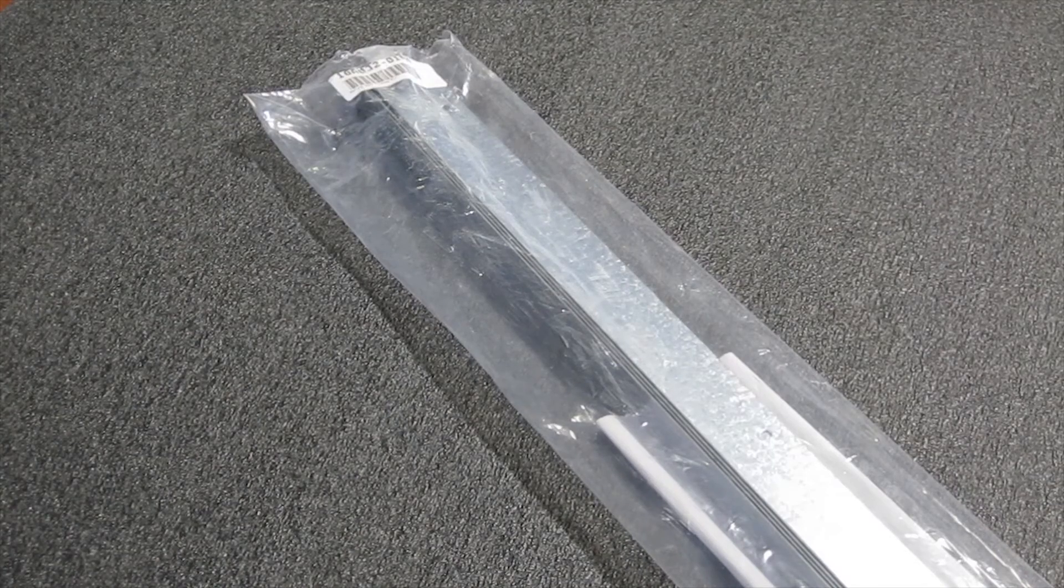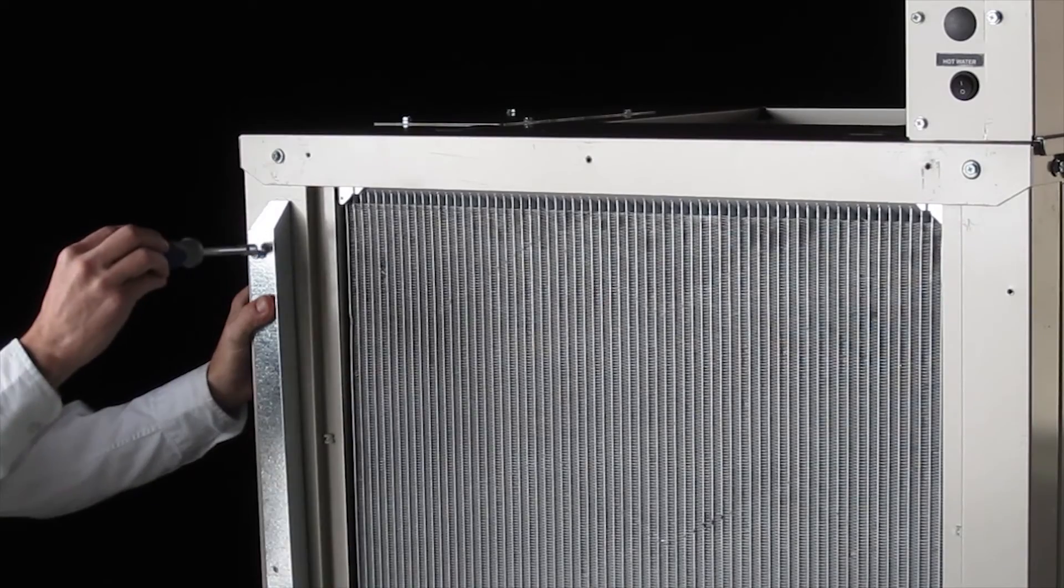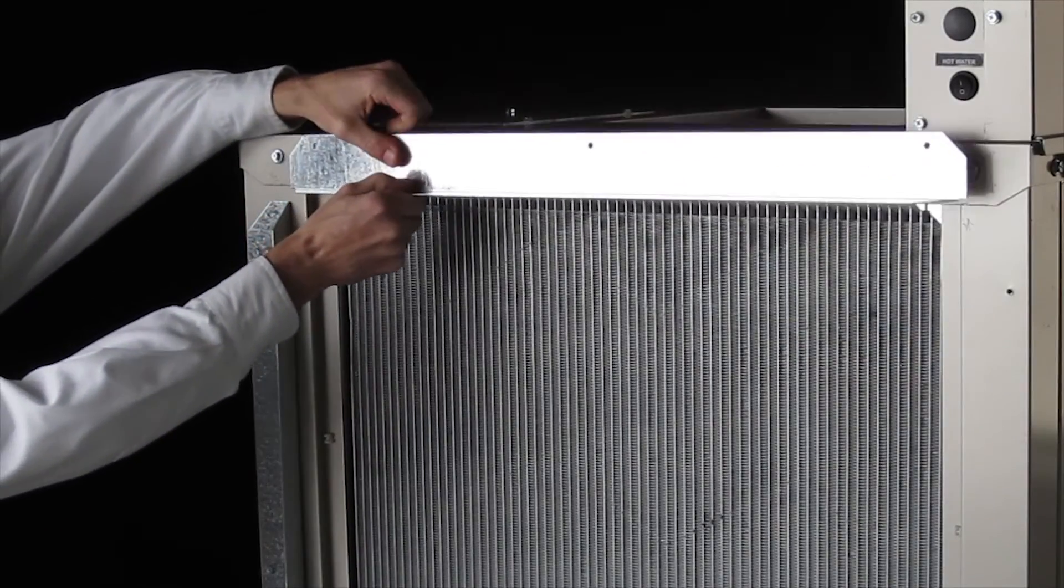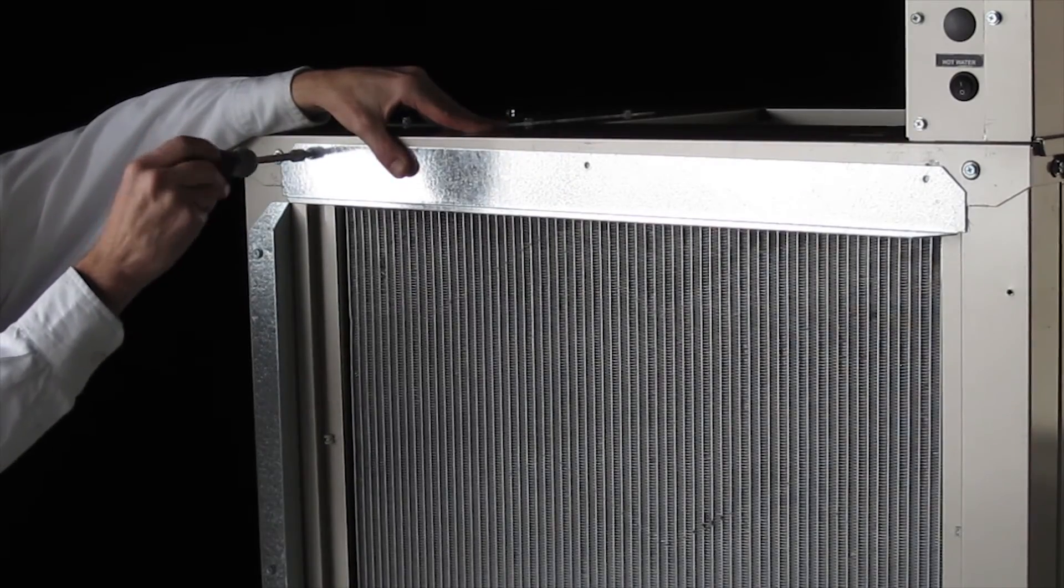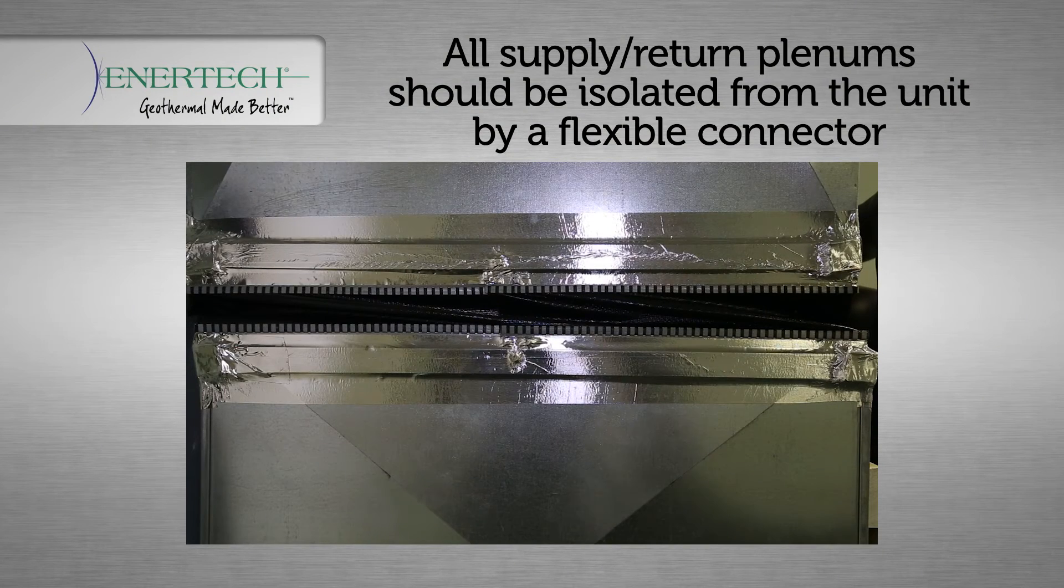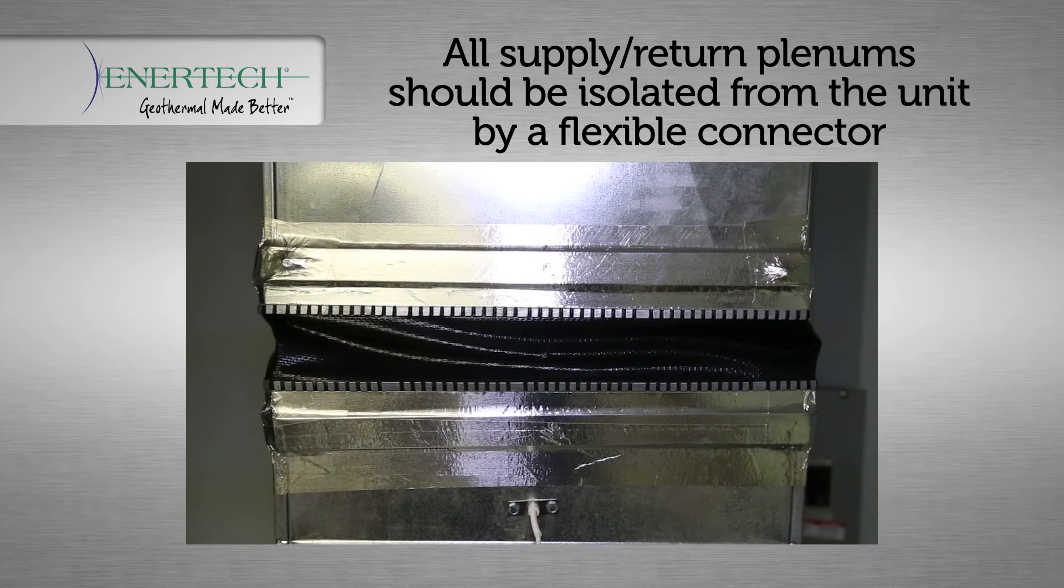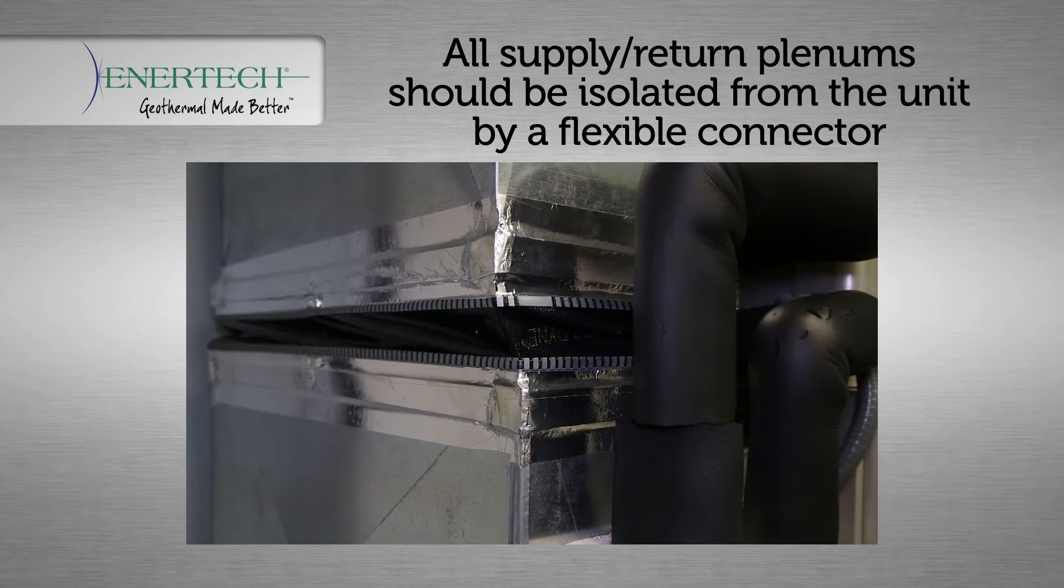As discussed in section 5 unit piping installation, install the return duct flanges provided in the kit package shipping inside the unit. Per the instructions, all supply return plenums should be isolated from the unit by a flexible connector or equivalent to prevent transfer of vibration noise to the ductwork. The flex connector should be designed so as to not restrict the airflow.